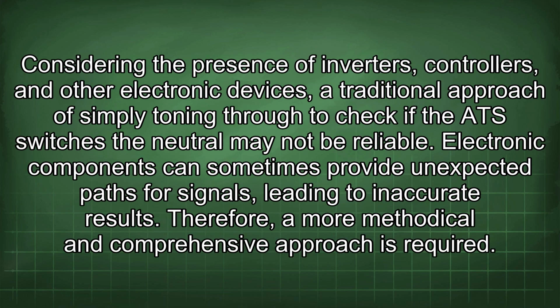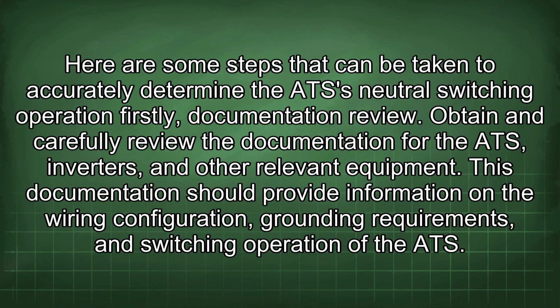Considering the presence of inverters, controllers, and other electronic devices, a traditional approach of simply ringing through to check if the ATS switches the neutral may not be reliable. Electronic components can sometimes provide unexpected paths for signals, leading to inaccurate results. Therefore, a more methodical and comprehensive approach is required. Here are some steps that can be taken to accurately determine the ATS neutral switching operation.